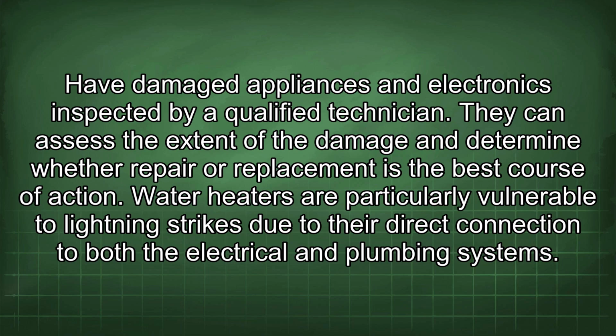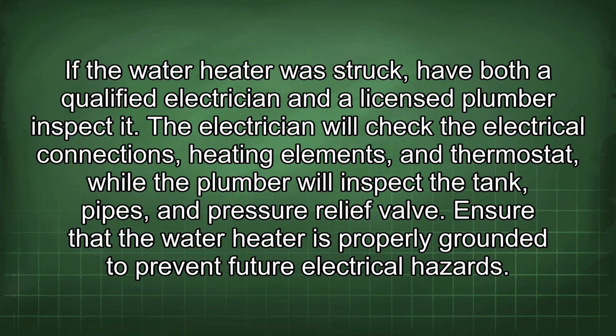They can assess the extent of the damage and determine whether repair or replacement is the best course of action. Water heaters are particularly vulnerable to lightning strikes due to their direct connection to both the electrical and plumbing systems. If the water heater was struck, have both a qualified electrician and a licensed plumber inspect it. The electrician will check the electrical connections, heating elements, and thermostat, while the plumber will inspect the tank, pipes, and pressure relief valve. Ensure that the water heater is properly grounded to prevent future electrical hazards.